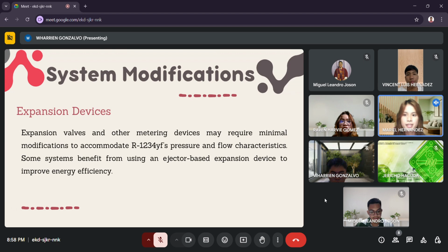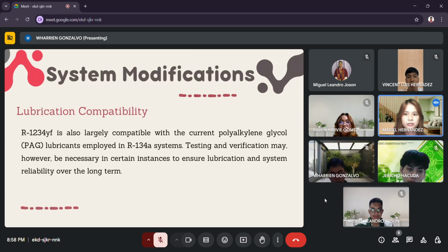Expansion devices such as expansion valves and other metering devices may require minimal modifications to accommodate R1234yf pressure and flow characteristics. Some systems benefit from using an ejector-based expansion device to improve energy efficiency. Lubrication compatibility is also one of the things that need to be considered. R1234yf is largely compatible with the current polyalkylene glycol, or PAG, lubricants employed in R134a systems. Testing and verification may, however, be necessary in certain instances to ensure lubrication and system reliability over the long term.